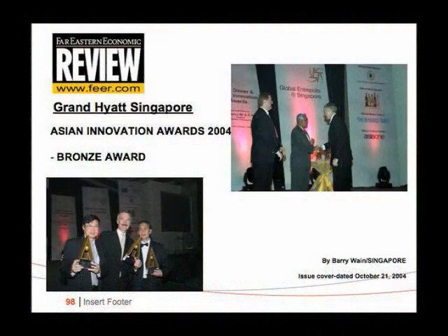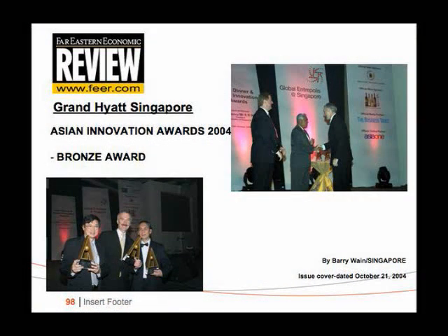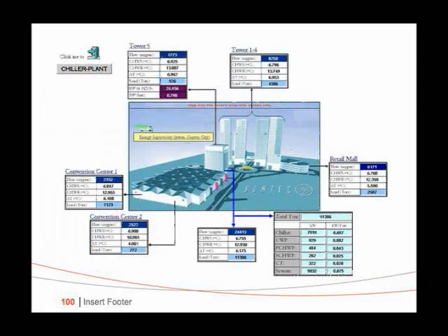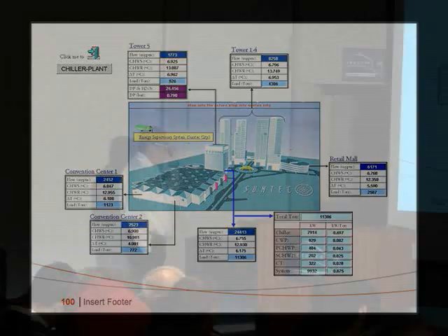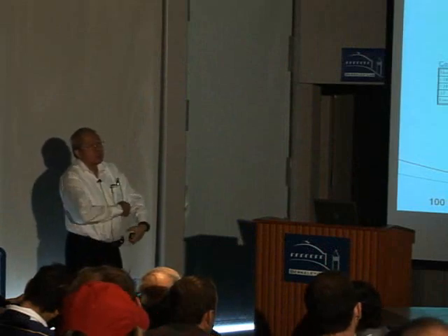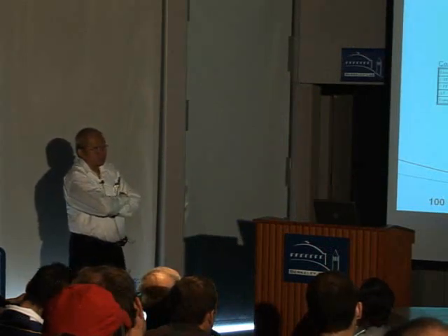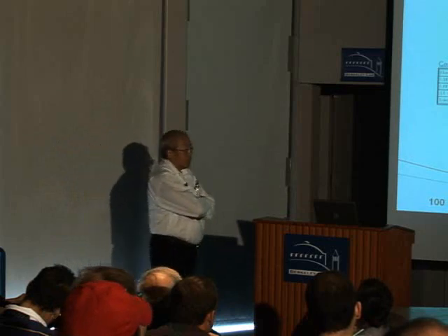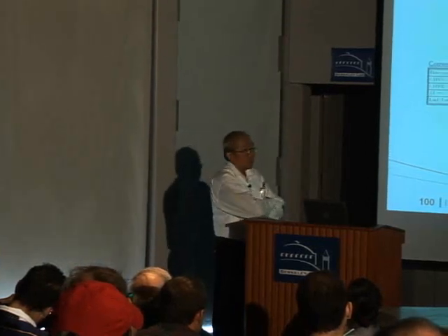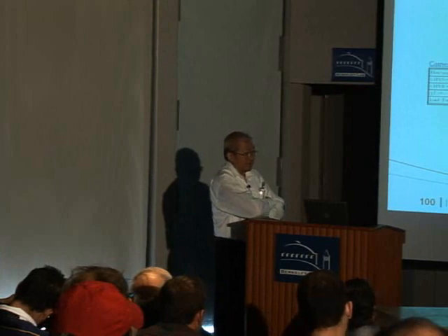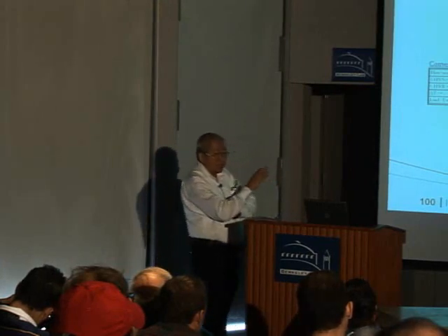Is this new? This is not new. The Grand Hyatt Singapore was also guaranteed at 0.58. That's 8 years ago. This is a big plant, 23,000 tons. 0.875. I had this interesting discussion with some gentleman from the ministry who says, we are encouraging the use of district cooling plants because it's more efficient, you know, economies of scale. And I said, no. All the district cooling plants are very bad. Not in the Michael Jackson sense, you know. Bad is not good. I mean, it's just bad is bad.